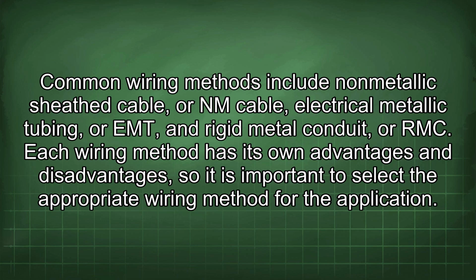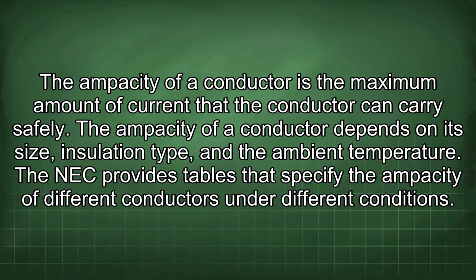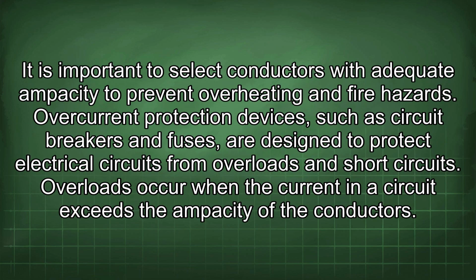for the application. The ampacity of a conductor is the maximum amount of current that the conductor can carry safely. The ampacity of a conductor depends on its size, insulation type, and the ambient temperature. The NEC provides tables that specify the ampacity of different conductors under different conditions. It is important to select conductors with adequate ampacity to prevent overheating and fire hazards.